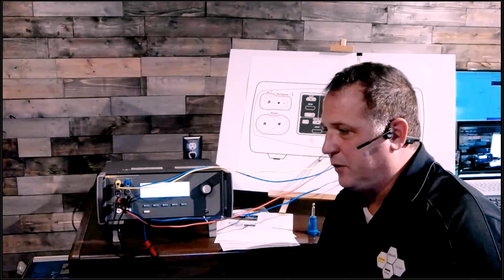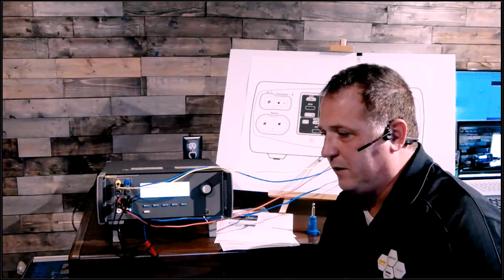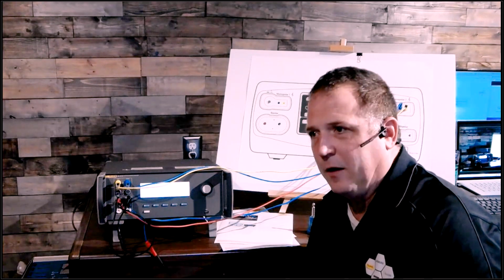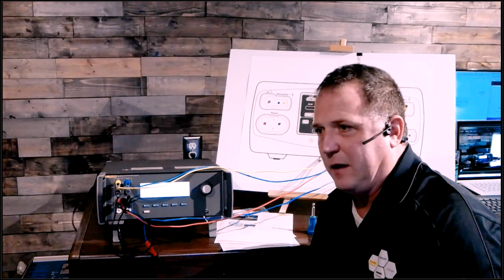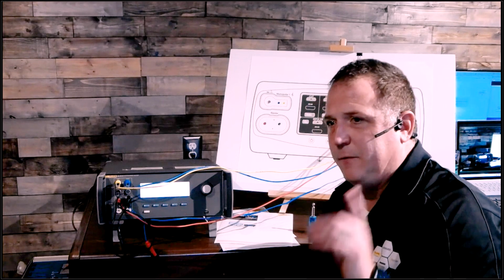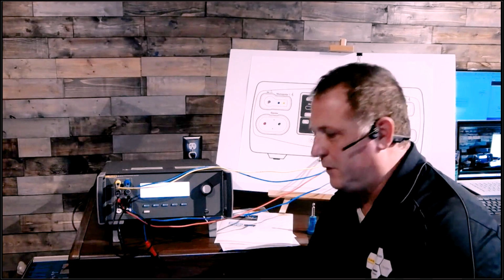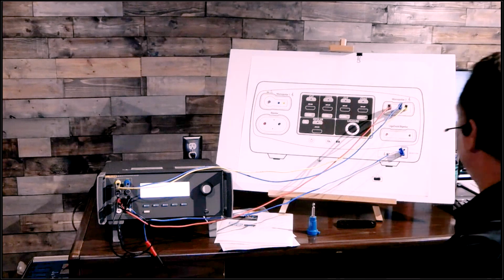I encourage you, if you suspect your ESU could be having an issue, test multiple points. Check your cut at 5, 10, 15, 20, whatever increment you feel necessary or your service manual dictates. We do a lot of assuming in the field that if the worst case scenario works, it's going to work across the full scale, but it's definitely a good thing to check that full range, especially if you suspect an issue with one of your ESUs.